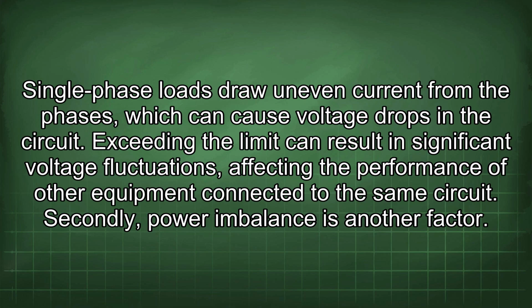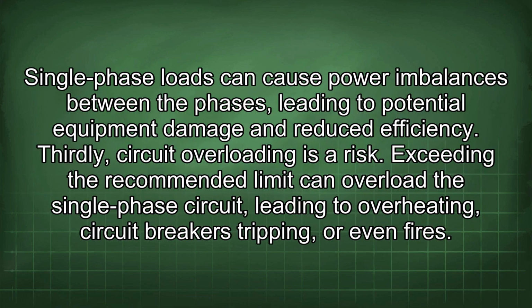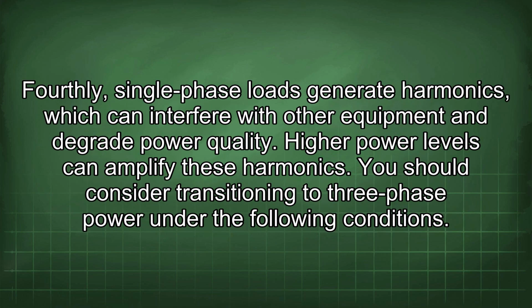Secondly, power imbalance is another factor. Single-phase loads can cause power imbalances between the phases, leading to potential equipment damage and reduced efficiency. Thirdly, circuit overloading is a risk. Exceeding the recommended limit can overload the single-phase circuit, leading to overheating, circuit breakers tripping, or even fires. Fourthly, single-phase loads generate harmonics, which can interfere with other equipment and degrade power quality. Higher power levels can amplify these harmonics.